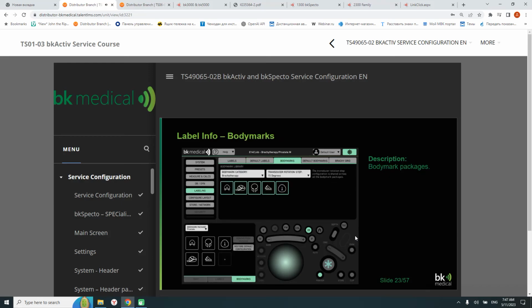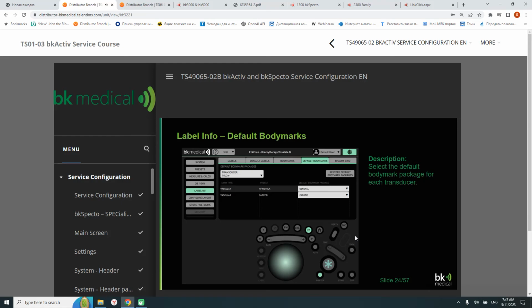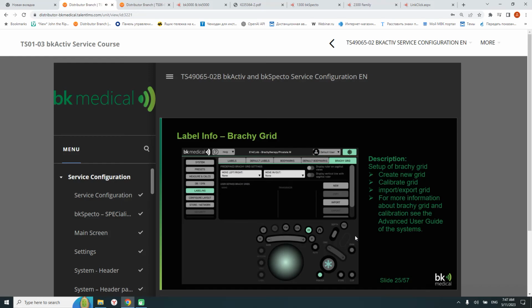Similar to the calculation and label packages, there are body mark packages which can be customized. In the Default Body Marks tab, it is possible to select which body mark package is default for all presets assigned to each transducer. In the Brachy Grid tab, it is possible to set up and software calibrate the brachy grid.